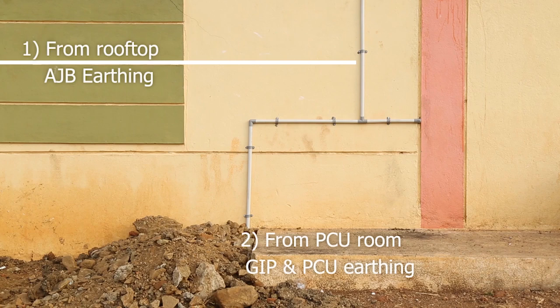One set of wire, positive and negative, goes inside the house to connect the power conditioning unit. One wire, green color, 10 square millimeter, through the pipe goes to the earth for earthing the array junction box.